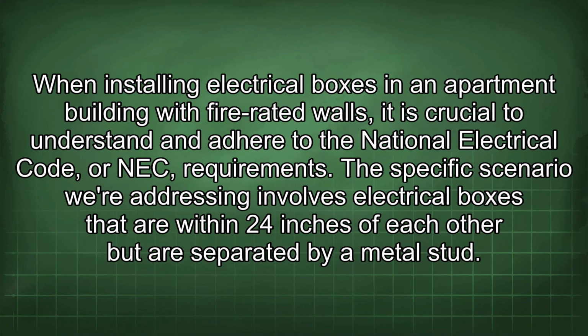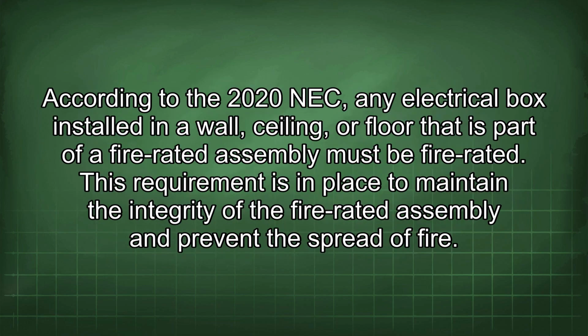When installing electrical boxes in an apartment building with fire-rated walls, it is crucial to understand and adhere to the National Electrical Code, or NEC, requirements. The specific scenario we're addressing involves electrical boxes that are within 24 inches of each other but are separated by a metal stud. According to the 2020 NEC, any electrical box installed in a wall, ceiling, or a floor that is part of a fire-rated assembly must be fire-rated. This requirement is in place to maintain the integrity of the fire-rated assembly and prevent the spread of fire.